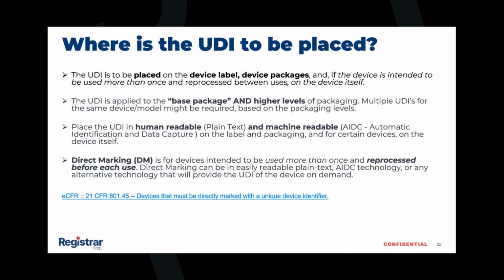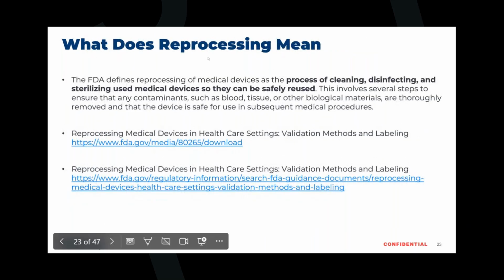If the device is intended to be used more than once and reprocessed for each use, it will be required to have direct marking. Direct marking can be easily readable plain text as well. What does reprocessing mean? The FDA defines reprocessing of medical devices as the process of cleaning, disinfecting, and sterilizing used medical devices so they can be safely reused. This involves several steps to ensure that any contaminants such as blood, tissue, or other biological materials are thoroughly removed and that the device is safe for use in subsequent medical procedures. These are the devices that require direct marking.